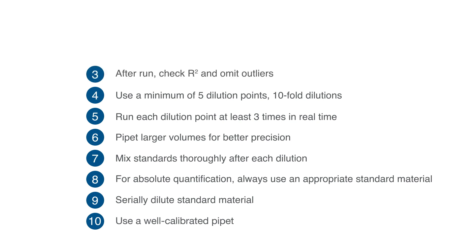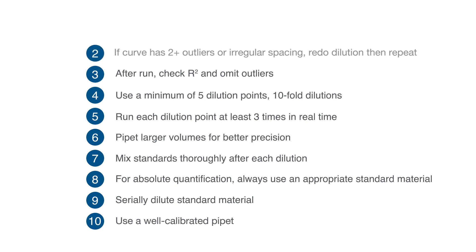Number 3: after the run, check your R-squared, look for outliers, and omit them. Number 2: if the curve has more than one or two outliers, or if the spacing between any of your points is irregular, redo the dilution and repeat the entire curve.